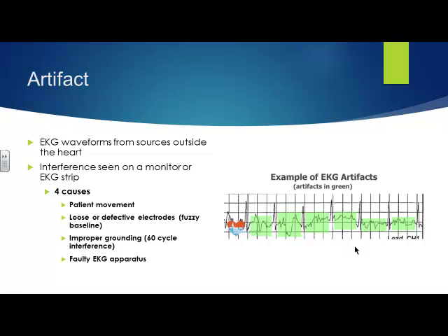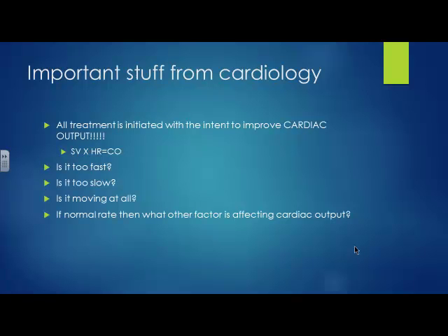In the case that you do have artifact, first thing you should do is get your patient to sit still. Second thing you need to do is check lead placement. Make sure that they're connected. See if you've got it all grounded correctly. And if you continue to see this, then you may have an ECG monitor issue. All right?